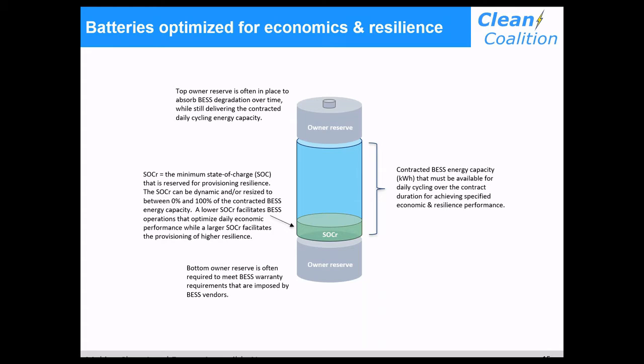The space in between is what you really need to keep in mind, and that is the usable capacity of the battery. When I say usable capacity, I'm not talking about day 1, I'm talking about the usable capacity at the end of year 10 or year 25. If you're in a 25-year power purchase agreement for a solar microgrid, you want to know the smallest level of energy capacity you'll have access to over that 25-year period. It's not what it is on day 1, it's what it is at the lowest point.